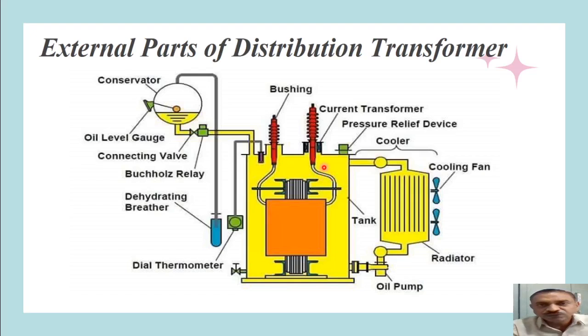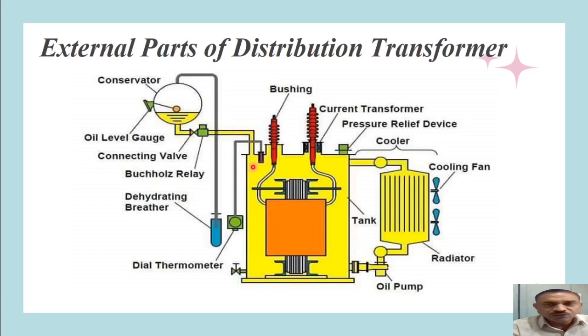The oil serves two functions: it insulates the windings and also provides a cooling medium for the whole transformer. A pressure relief device is provided at the top to protect the transformer in the event of any severe fault inside the tank. The oil tank is connected via a ventilating pipe to another tank called a conservator or external tank, which holds oil inside it. The conservator is provided because when the transformer operates at rated loading conditions, there are iron losses and copper losses that produce heat.